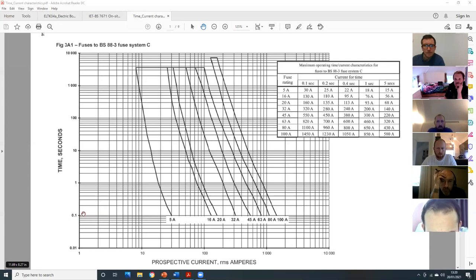Yeah, it's a little bit about how closely and how accurately you read a logarithmic scale, but basically the procedure is 0.1, 0.2, 0.3, 0.4. We're somewhere between 90 and 100. As you'll see on this scale, halfway between 1 and 10 isn't actually 5, it's more like 3. So it's quite likely that it's smaller. But again, if you'd come up here, you could have seen that it does actually take 95 amps. The table makes it, for this particular question, bang on, 0.4 of a second.